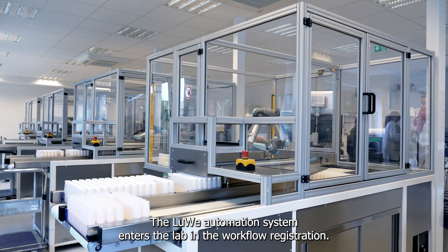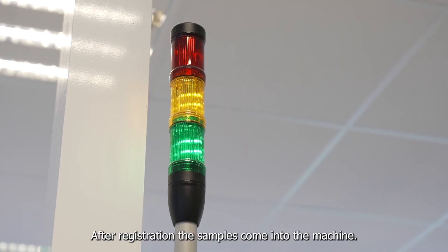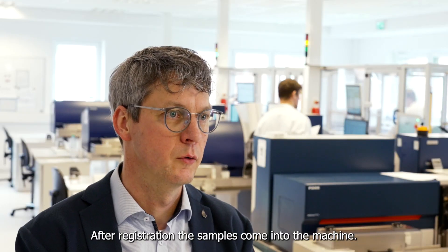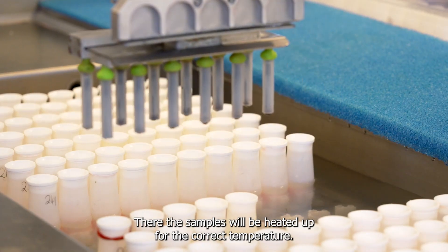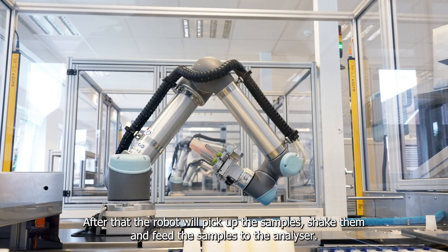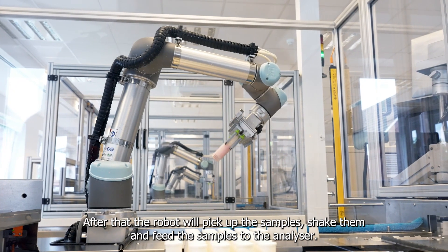The LuWe automation system enters the lab in the workflow of the registration. After registration, the samples come into the machine. The robot will pick up the samples, put them in the water bath, and the samples will be heated up to the correct temperature. After that, the robot will pick the samples, shake them, and feed the samples to the analyzer.